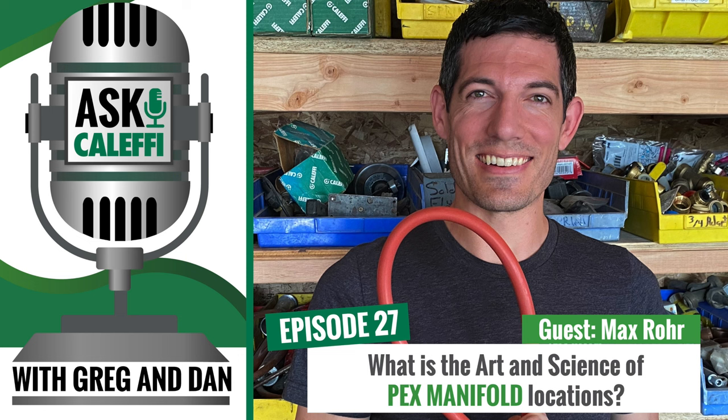It sure is. I actually did a job one time with a row panel system on the main floor of the home, with a basement below it. We did a row panel extruded aluminum floor system, and I was filling the system and it was leaking into the basement. And remember, that panel is sandwiched between the subfloor and the finished wood floor. Oh no. We used the thermal imaging camera and I could see the water start to come out of the PEX, and I put a piece of tape over the spot, and the wood floor guy came in and pulled it out, and it was right there. With that thermal imaging camera, I was directly over that nail.